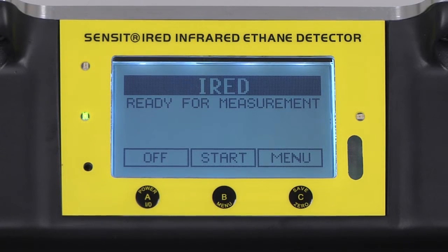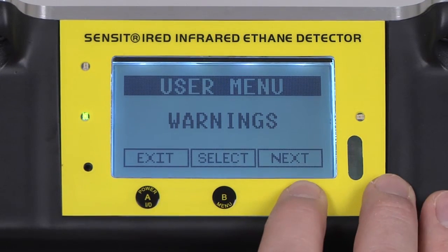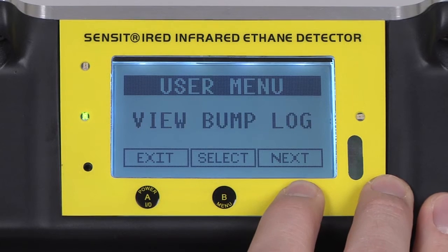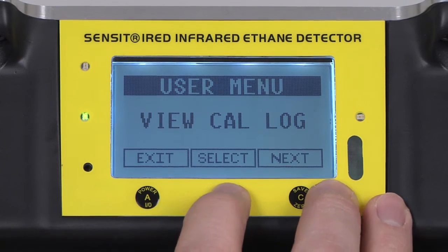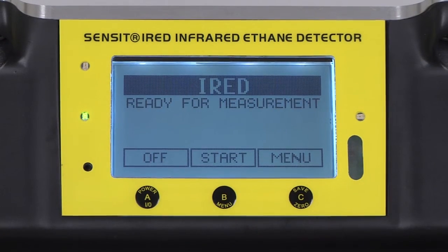To verify the calibration date of the IRED, enter into the menu by pressing and releasing the C button and scroll by pressing and releasing the C button until View Cal Log appears. Select by pressing and releasing the B button and the most recent calibration date will be displayed. Exit back to the working display by pressing and releasing the A button.